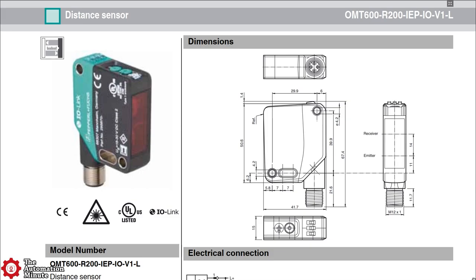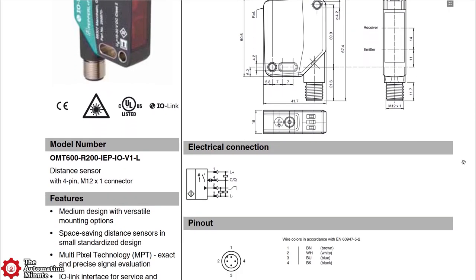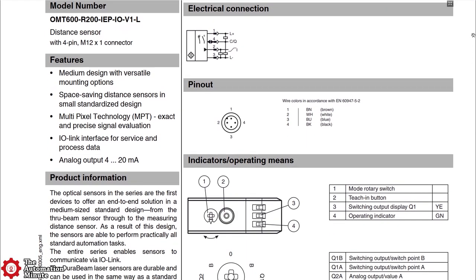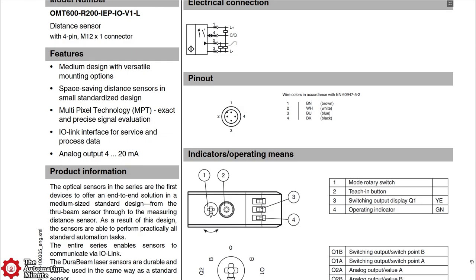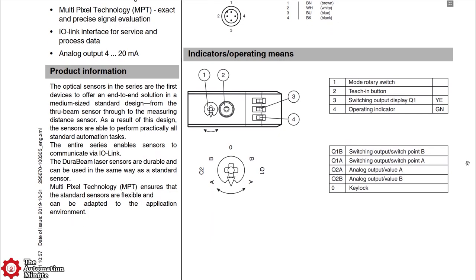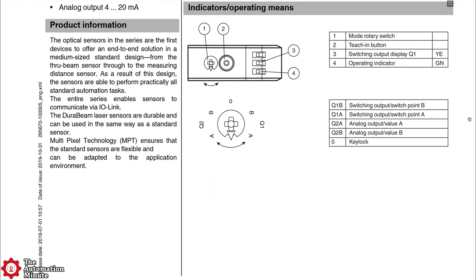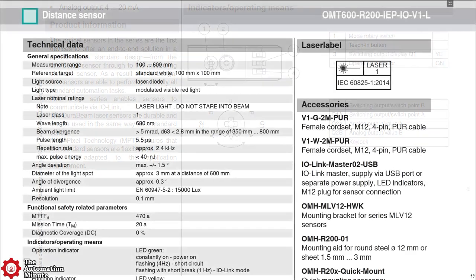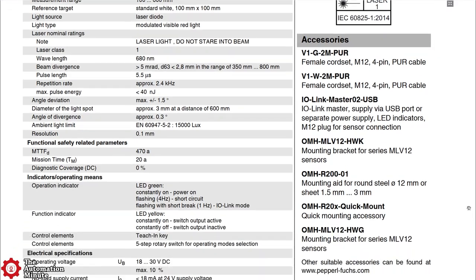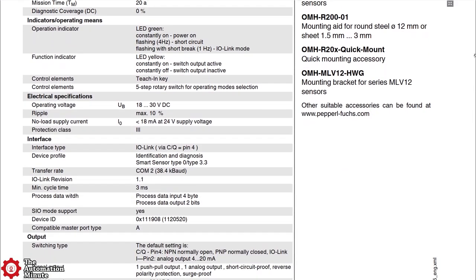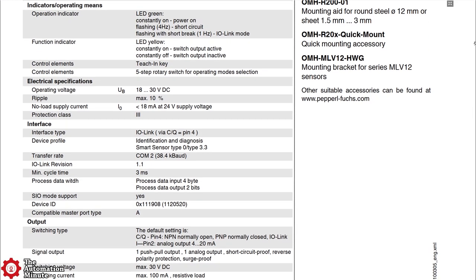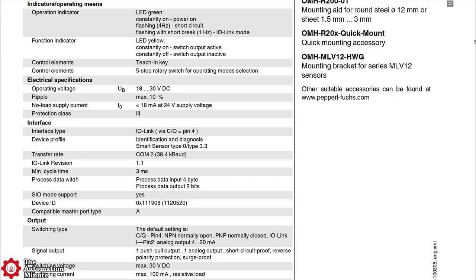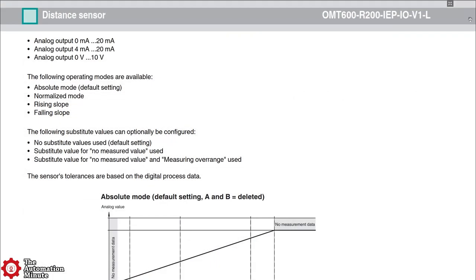It's an IO-Link enabled class 1 laser diode distance sensor with an operating voltage range of 18 to 30 volts DC and a sensing range of 100 to 600 millimeters with an accuracy of approximately 0.1 millimeters. It has both NPN normally open and PNP normally closed outputs, as well as an analog output that comes set to 4 to 20 milliamps out, but can also be set to 0 to 20 milliamps or 0 to 10 volts DC.